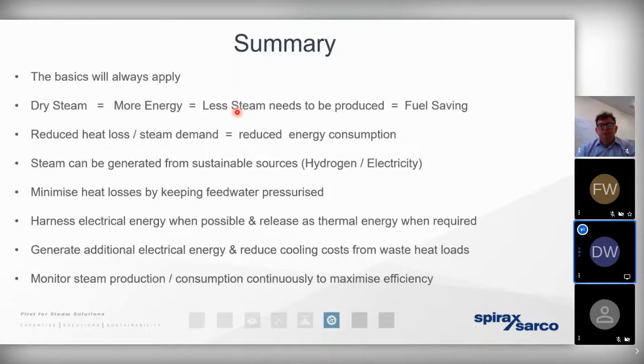So just to summarize very, very quickly what we've gone through today, the first point I'd like to make is that before we move towards a situation where we're looking at new concepts that we could employ in future years, the basics, they're always going to apply. They've always got a place, regardless of how we're generating steam. We want to reduce demand. We want to do everything we can to keep the steam as dry as we possibly can. Simply put, the drier the steam, the more energy. If we can reduce the demand for steam or utilize the steam at the process more efficiently, if we're consuming less steam, we're consuming less fuel, and we've got fewer carbon emissions.